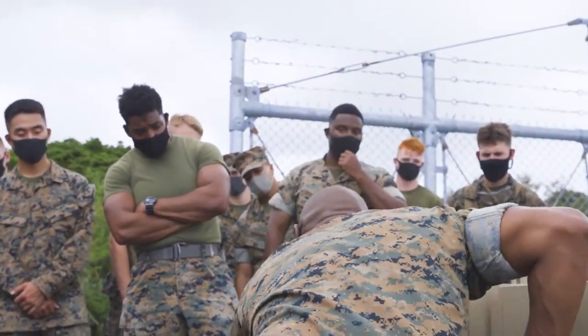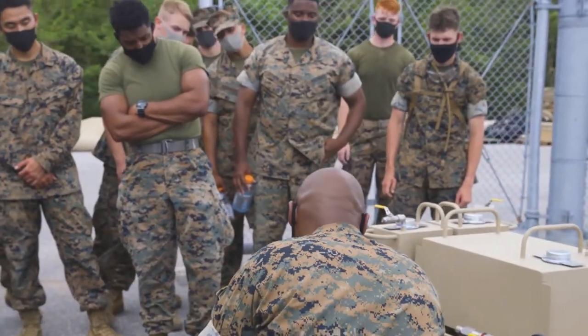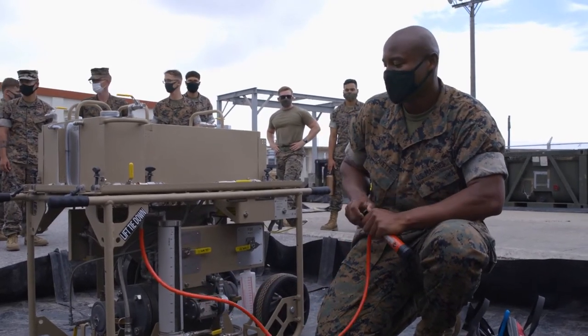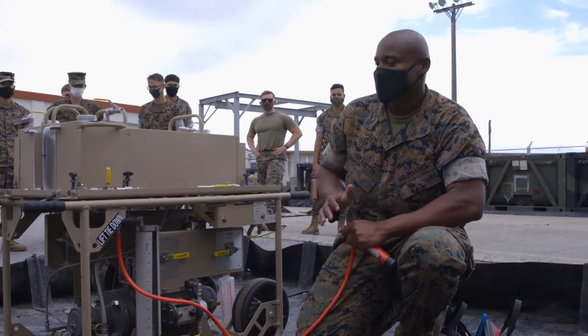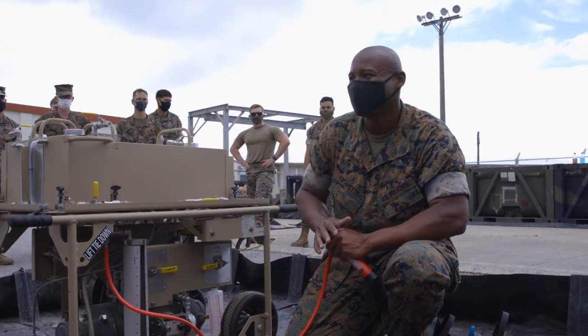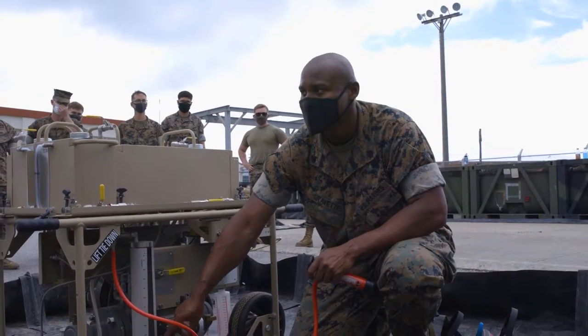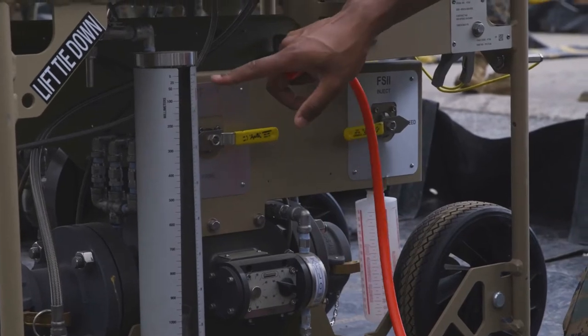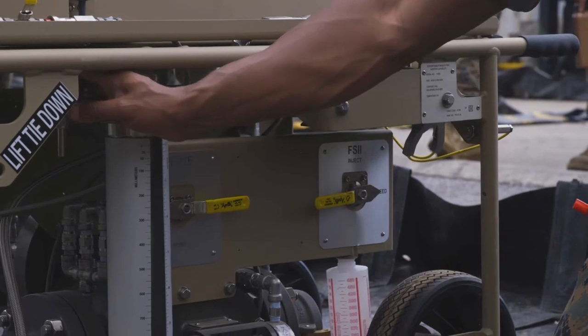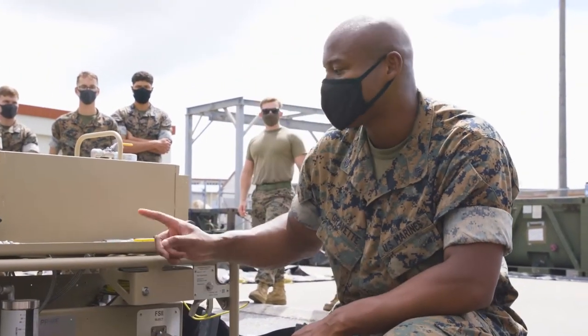If it's your first time priming the lines, you're going to hook up your hose, you're going to put it on the vacuum side of the pump, and start expressing. As you're expressing — these are empty so you're not going to see it right now — but as you're expressing, you will eventually start seeing fluids start bubbling in. You can go ahead and remove this and just watch until the fluids get to zero. Once they get to zero, go ahead and just close this. We'll go through with all these lines closed.